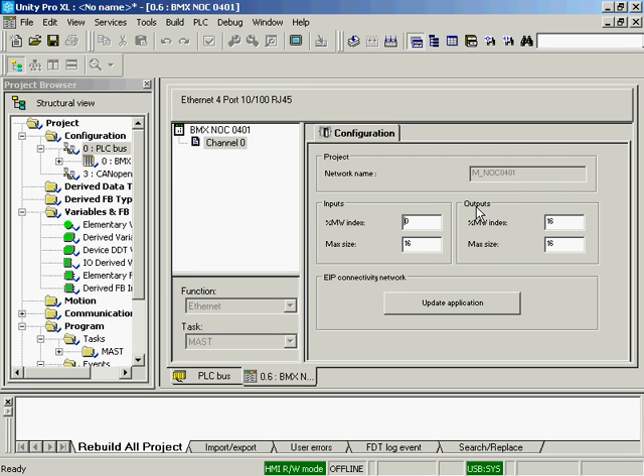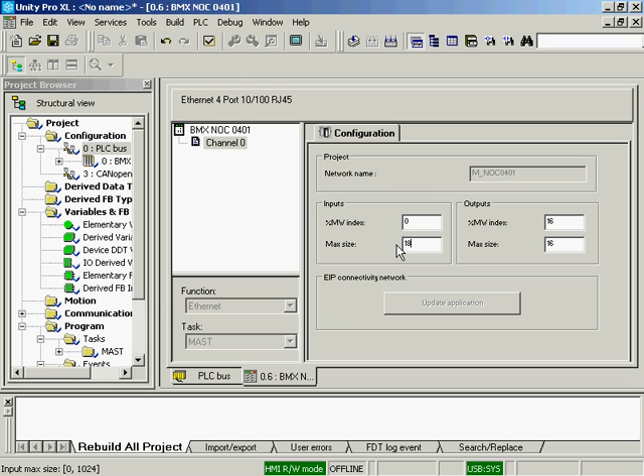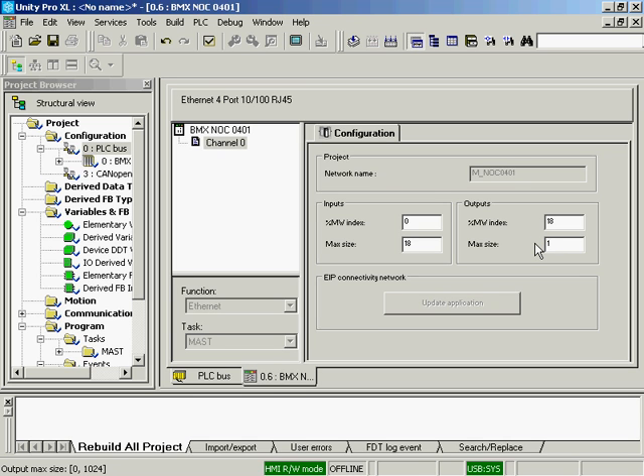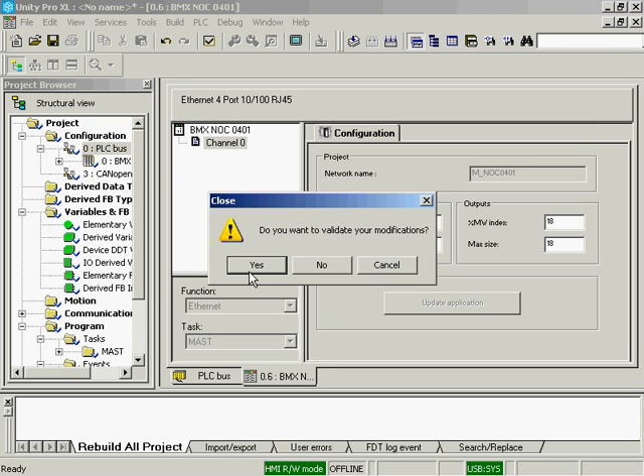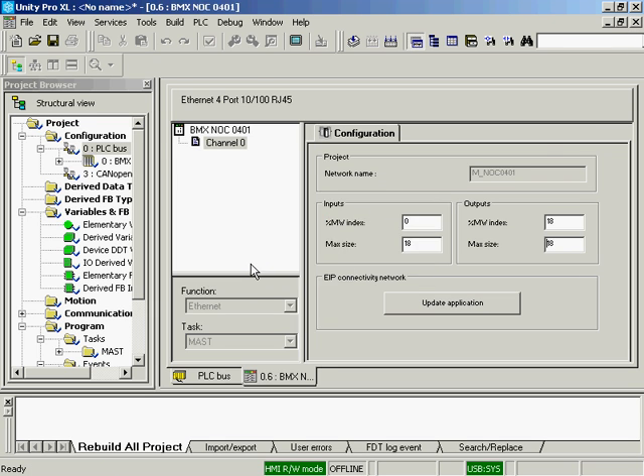And when I double-click the module, we'll go in and configure the memory that it's going to take for Ethernet IP or Modbus TCP. We're going to use 18 registers, two inputs, two additional inputs for the ATV32, and two additional outputs. That will be for the control word, the reference speed, the status bits, and the running speed. And we'll accept those modifications.